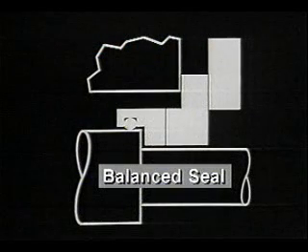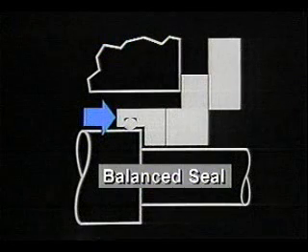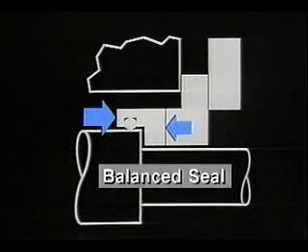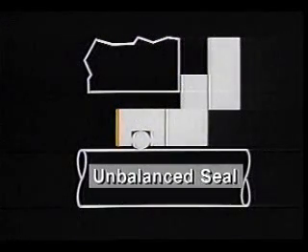Now, let's move to the concept of seal balance. Seal balance is a mechanical arrangement built into the seal. Balance reduces the amount of axial closing force working to keep the seal faces closed. There is only a slightly higher closing force than opening force. Seal balance reduces the closing force by changing the area that the stuffing box pressure is working on to close the seal faces.